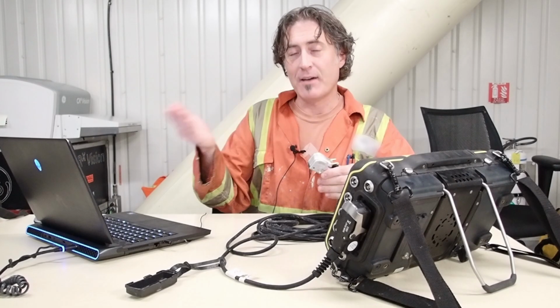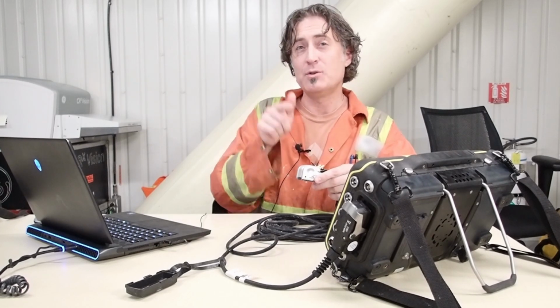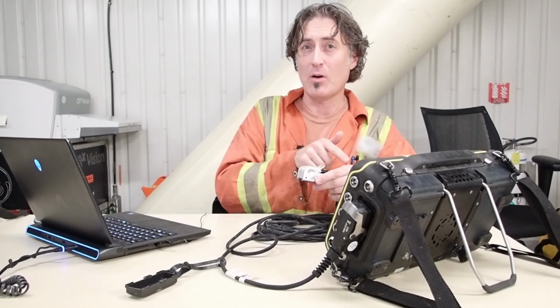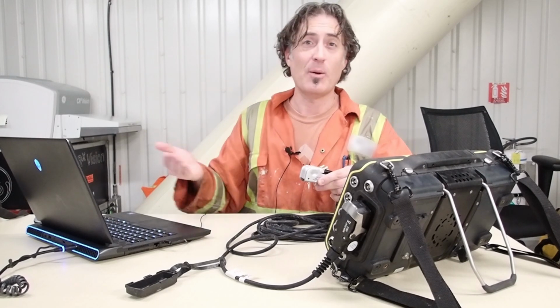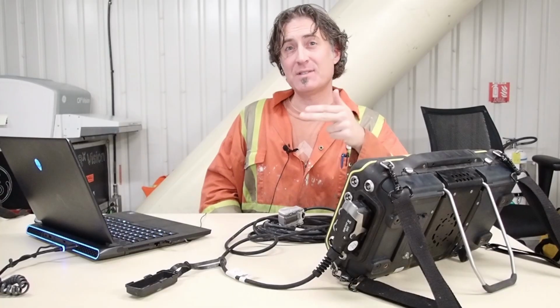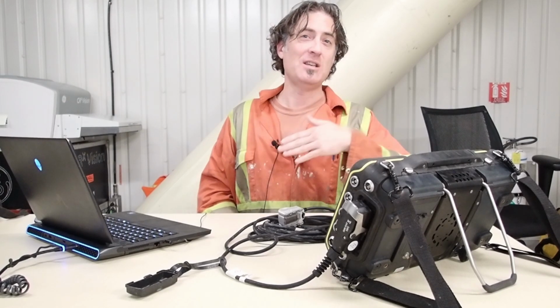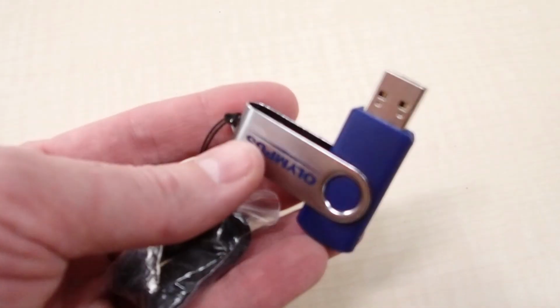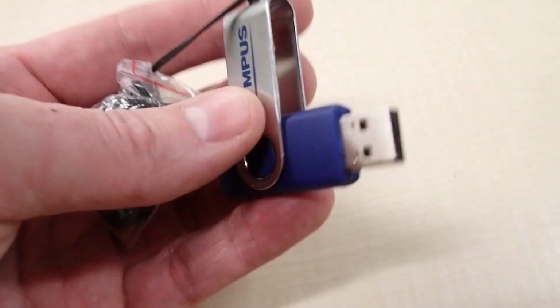Now, Olympus, evident, has done this so that you don't need the pulser receiver option, so you can actually use this on an Omniscan SX. But this means you have to tell the instrument to fire on the even elements and listen on the odd elements. That's not something we are normally able to do on the instrument, so Olympus gives you a USB key with all the setup files on it.